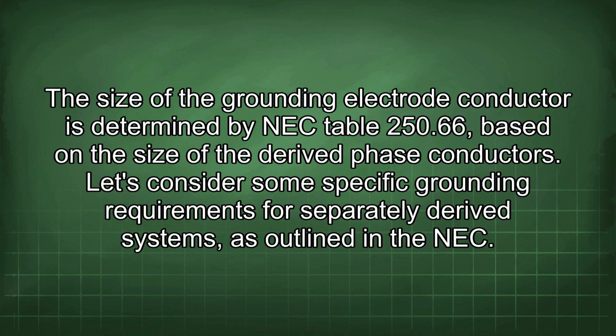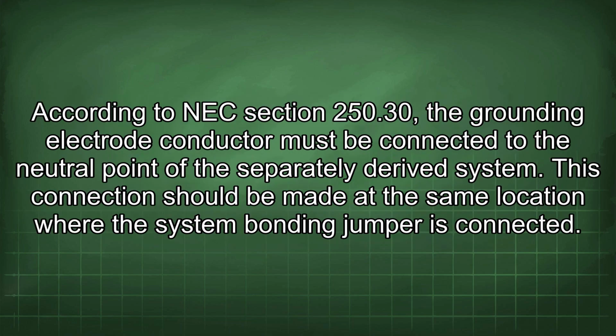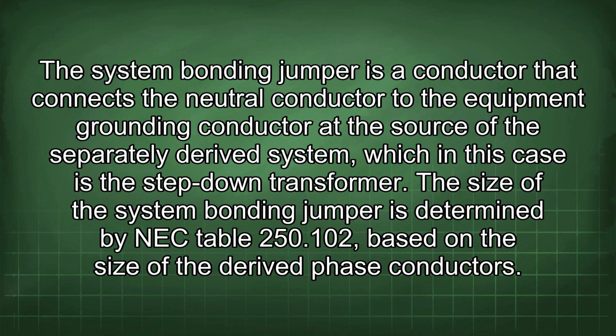Let's consider some specific grounding requirements for separately derived systems, as outlined in the NEC. According to NEC section 250.30, the grounding electrode conductor must be connected to the neutral point of the separately derived system. This connection should be made at the same location where the system bonding jumper is connected. The system bonding jumper is a conductor that connects the neutral conductor to the equipment grounding conductor at the source of the separately derived system, which in this case is a step-down transformer. The size of the system bonding jumper is determined by NEC Table 250.102, based on the size of the derived phase conductors.